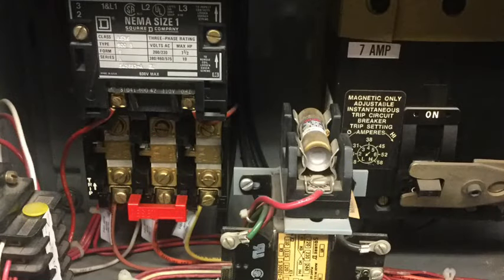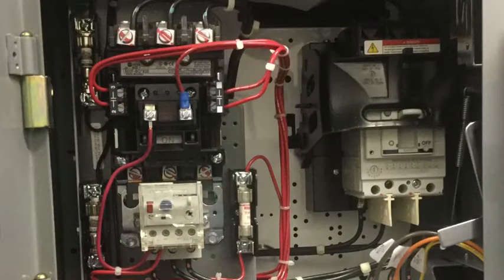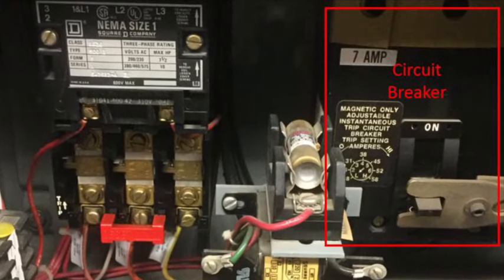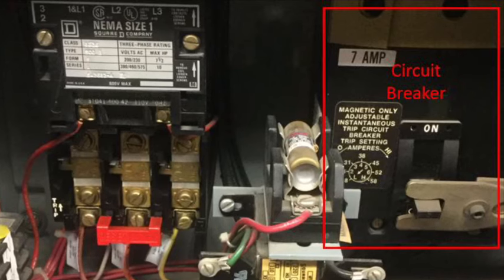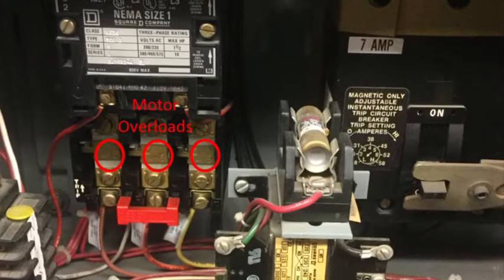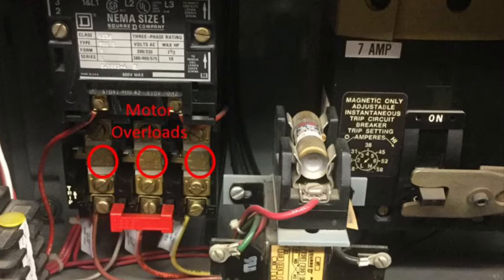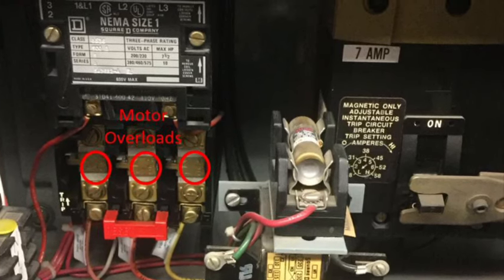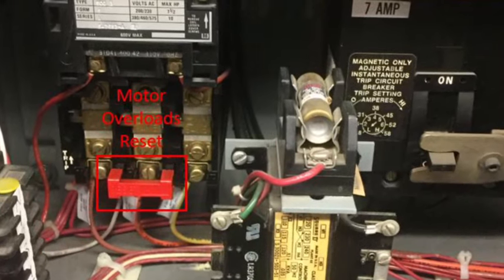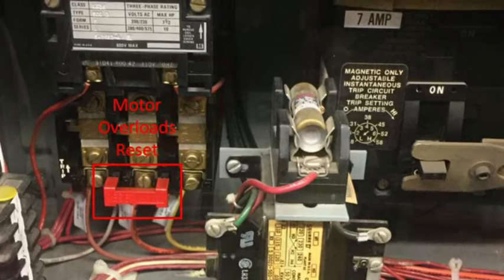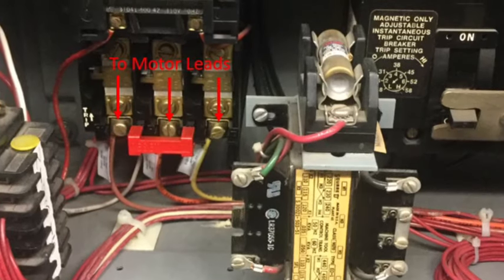Despite the various manufacturers, motor starters have basically the same components and serve the same purpose. Take your time. Familiarize yourself prior to working on this equipment. The circuit breaker is sized to protect the wiring and components of the starter. The motor overloads are sized to open if 125% of the motor's full running amperage has been exceeded. The overload reset button. Terminals going to the motor leads.